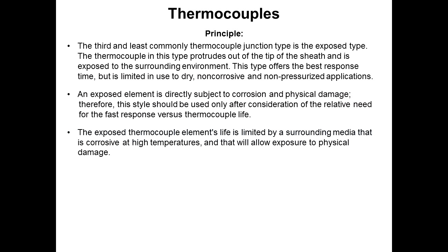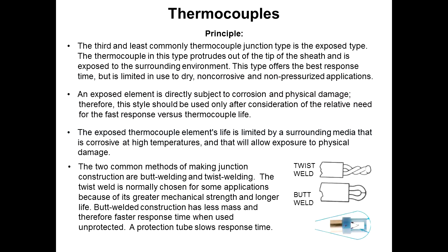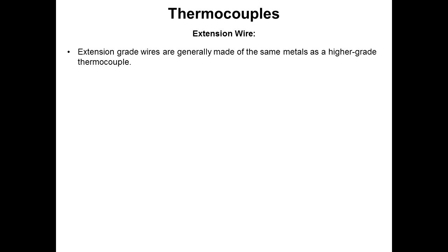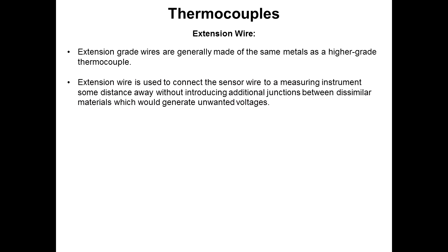kept in consideration. The two wires are twisted and then welded, or the two wires are butt welded together. We use them in a number of air probes on handheld instruments because they're much faster in response. Extension wires are usually higher grade material made of the same metals as what's called special limits of error thermocouples. That's to transmit your voltage from the probe out to a controller or a recorder.